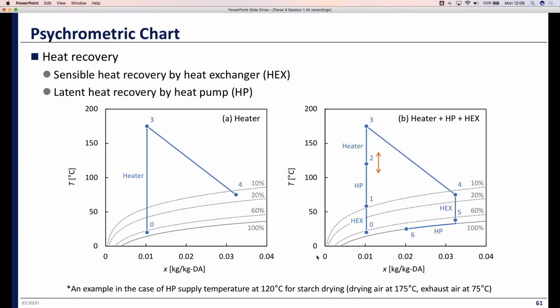I will explain the outline of the heat recovery system by using a psychrometric chart. Here is an example in the case of starch drying with air at 175 degrees C and exhaust air at 75 degrees C. The left chart shows the existing system without heat recovery. First, fresh air of state point 0 is heated by burner or steam. The heated and dried air of state point 3 is supplied to the dryer. The air becomes humid and the air temperature decreases. The exhaust air of state point 4 is wasted to the ambient.